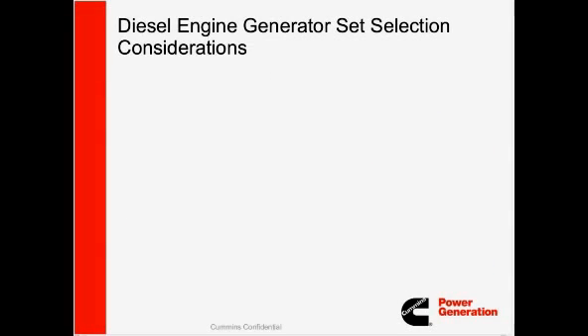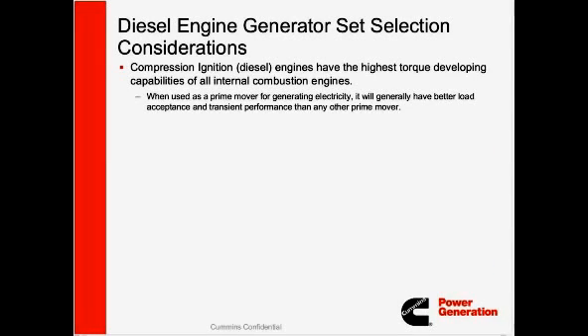So when we're talking about diesel generators, there are a few benefits and advantages for diesel. The main point is really that compression ignition, or diesel engines, have the highest torque developing capabilities of all internal combustion engines. This is why you see diesel being used in many industrial and commercial applications. When used as a prime mover for generating electricity, it will generally have better load acceptance and transient performance than any other prime mover. This high torque capability of the diesel engine is what makes it the main selling point for using it in standby applications.